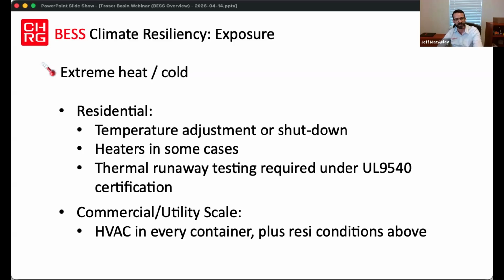So these battery systems need to be able to handle that. They used to simply shut down at certain temperature set points. Increasingly, we're seeing advanced systems where they'll start limiting the max charge rate or discharge rate based on the temperature instead of just a hard shut off, which is great. It really allows you to operate right up to the max limit of that device on the high end.